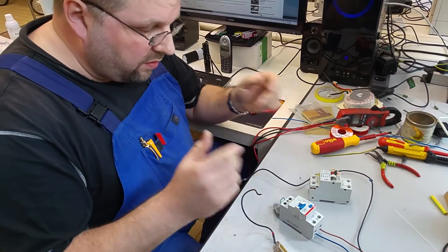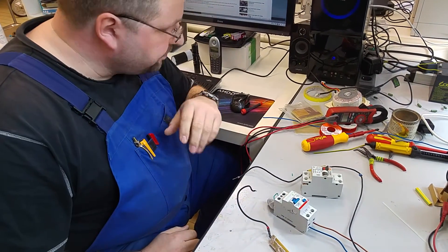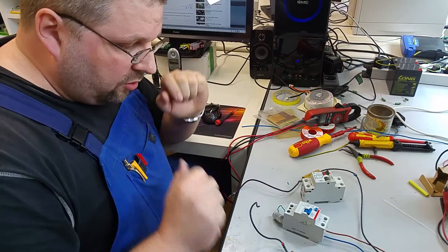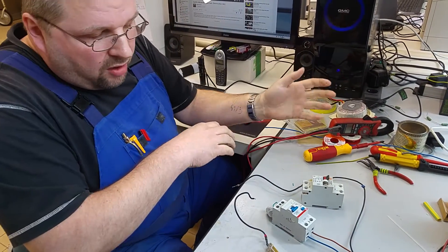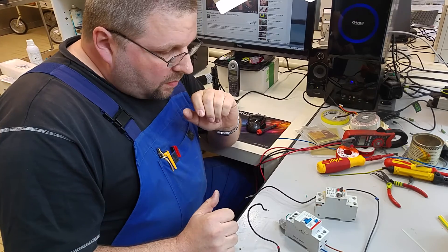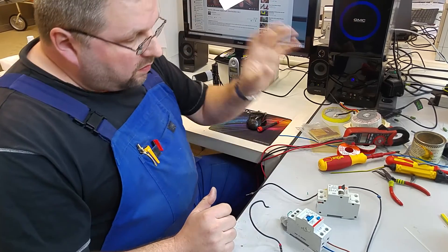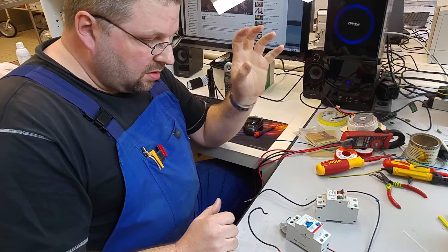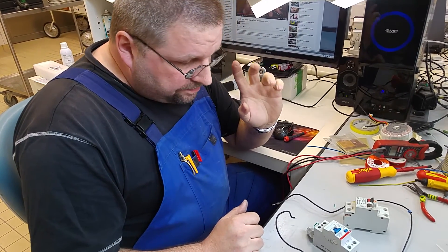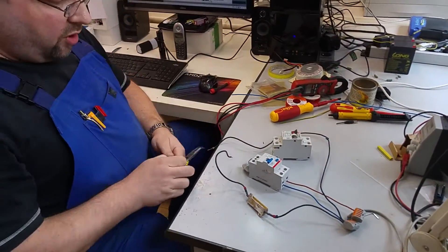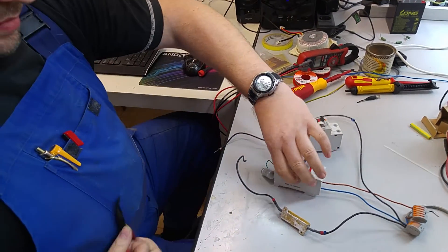That's basically it. I could grab another RCD, it would behave exactly the same. I could put this on this, it would still not trip. Maybe I grab another one and it would behave slightly different, but who really knows which type of RCD is built in his distribution panel, if there is an RCD at all. So you have to be careful, not to rely on the RCD tripping in case of failure, because like I showed you, it wouldn't trip in any case.